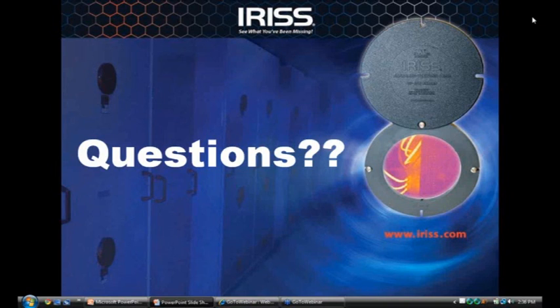But I do find a lot of my customers now are moving more towards an ultrasound port, primarily in their transformers or switchgear that's sealed. But even in their standard switchgear now, they're putting the ultrasound port because they want a standardized collection point for their ultrasound data, the same way as an infrared window is a data collection point for an infrared camera. So they're qualifying that you go to the ultrasound port, you take your data in such a way, you make your recordings, you put it in the file, but by taking it at the same point every time, the quality of the data and the trending is much higher.